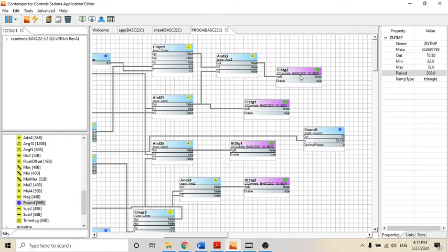But what I wanted to show mostly was heating and cooling, which is done in 2 stages: cooling stage 2, cooling stage 1, heating stage 1, heating stage 2. I added this other block here just to make it easier to see what the actual temperature is right now. It's only connected over there to the same ramp controller, and it gives us, rounded, what the temperature is. Currently 74 degrees.